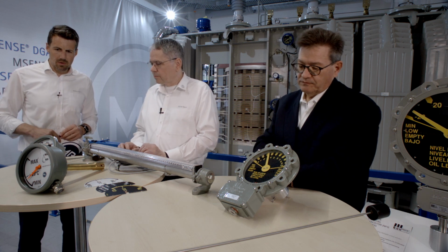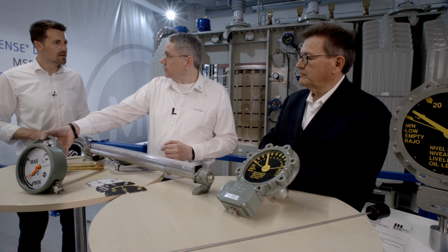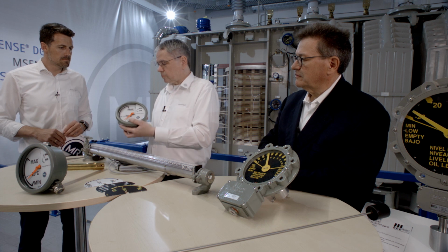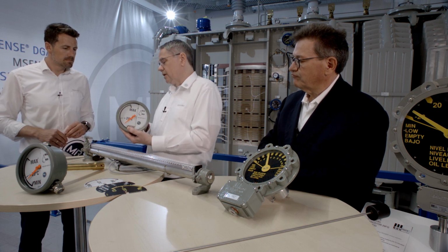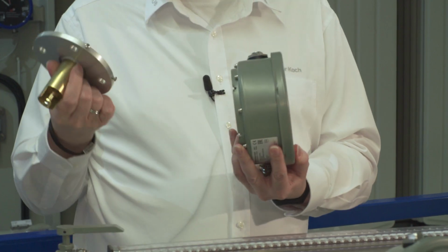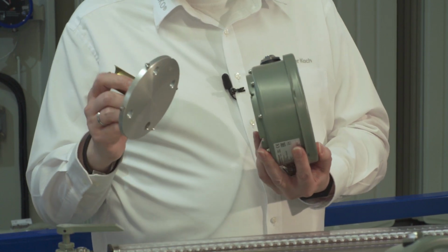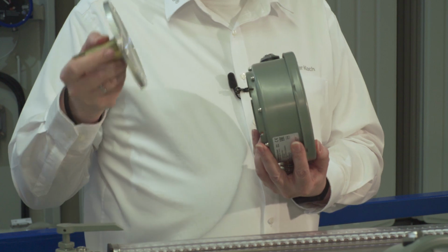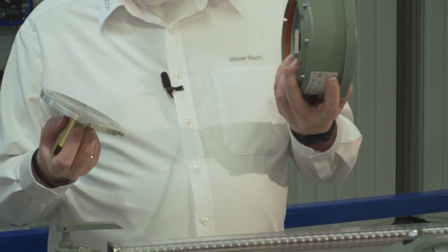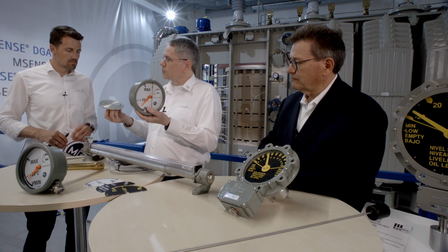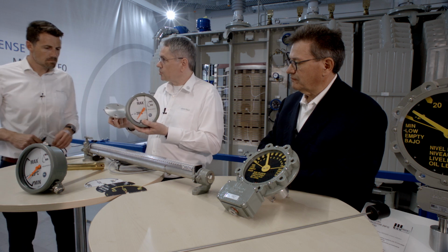That device here? So this is the MTO series. Yeah, this kind of device. We have here two parts. We have a flange part, which is mounted in the tank on the transformer. There's a float mounted on the oil. And you can remove the indication unit for transport or if something is damaged, for example.